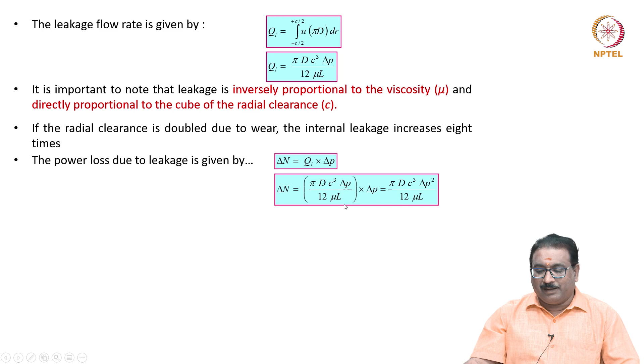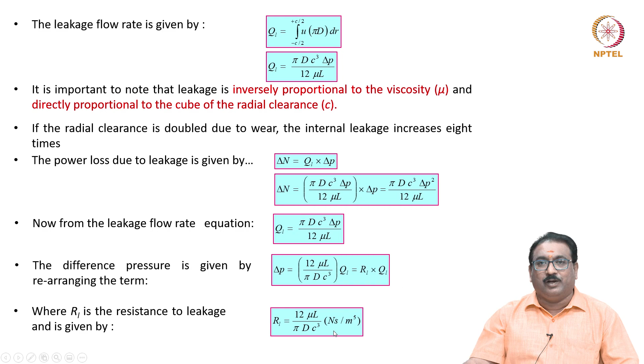Now, from the leakage flow rate equation, the same equation I am writing here, the differential pressure is given by rearranging the terms. Here I want delta P, friends. Delta P is the pressure drop across the leakage path. Delta P equal to what? 12 mu will go this side: 12 mu L divided by pi d c cube, into QL. Here 12 mu L by pi d c cube is a constant term for the particular combination of spool and bore. That is why I am taking RL into QL. Here RL is the resistance to leakage and is given by 12 mu L by pi d c cube, in Newton second per m to the power of 5. Substitute all the values in the same units.